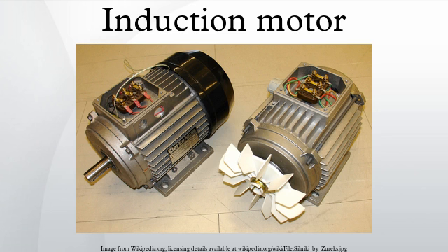Torque. Standard torque. The typical speed-torque relationship of a standard NEMA design B polyphase induction motor is as shown in the curve at right. Suitable for most low-performance loads such as centrifugal pumps and fans, design B motors are constrained by the following typical torque ranges: breakdown torque, 175 to 300% of rated torque; locked rotor torque, 75 to 275% of rated torque; pull-up torque, 65 to 190% of rated torque.